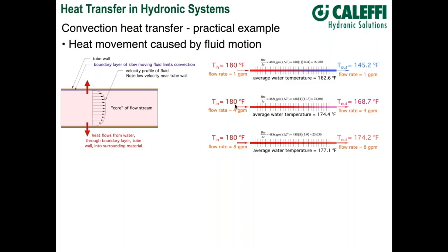Now take the same fin tube, same supply water temperature, but boost the flow rate to 4 GPM. The outlet temperature actually increases — the delta T has decreased, but remember delta T is only one factor in the rate of heat transfer; flow rate is the other. The average water temperature based on 180°F in and 168.7°F out goes up to 174°F. Increasing average water temperature in any heat emitter increases its heat output. We've gone from roughly 17,000 to roughly 22,000 BTUs per hour simply by increasing the flow rate — no change in water temperature, just a thinner boundary layer and better heat transfer.